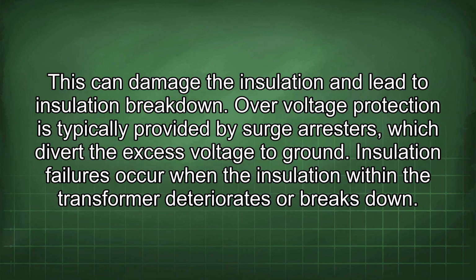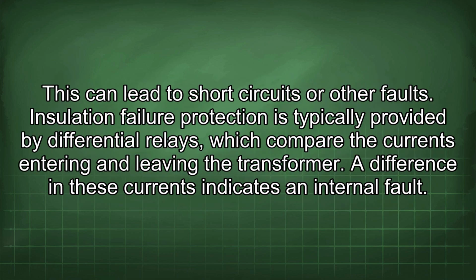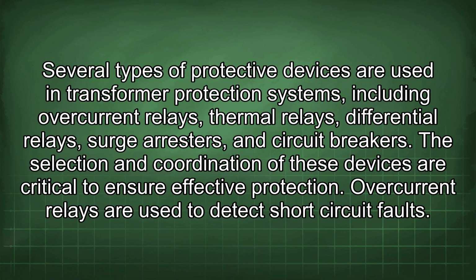Insulation failures occur when the insulation within the transformer deteriorates or breaks down. This can lead to short circuits or other faults. Insulation failure protection is typically provided by differential relays, which compare the currents entering and leaving the transformer. A difference in these currents indicates an internal fault. Several types of protective devices are used in transformer protection systems, including overcurrent relays, thermal relays, differential relays, surge arresters, and circuit breakers. The selection and coordination of these devices are critical to ensure effective protection.